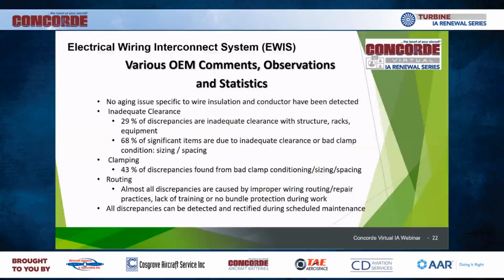Let's look at various OEM comments, observations, and statistics recorded during some of these inspections. We found no aging issue specific to wire insulation and conductor. Inadequate clearances were found in 29% of the discrepancies, between the structure and any wire or racks surrounding it. 68% of significant items were due to inadequate clearance. Again, bad clamp conditions, sizing, and spacing — 43% of the discrepancies found were from bad clamp conditions. And the routing: almost all discrepancies are caused by improper wire routing, repair practices, or lack of training.